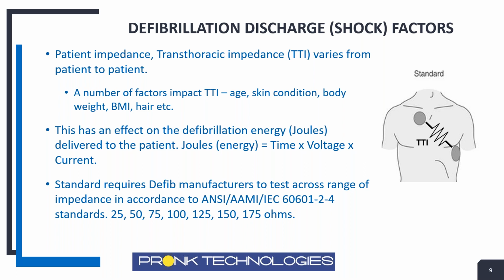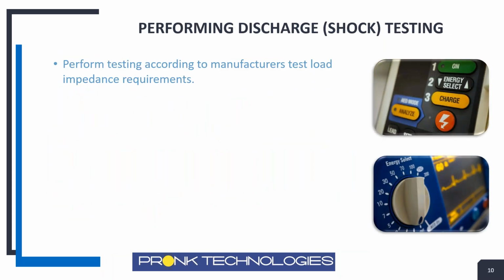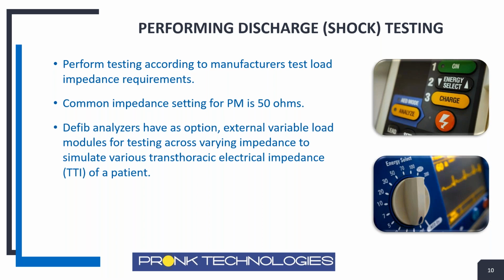So when we're servicing these devices, it's important that we have that in the back of our minds and that we verify what impedance load the manufacturer wants me to use to service this defibrillator. The most common impedance is 50 ohms. Most all defibrillator analyzers have an impedance set for 50 ohms, and that's designed for PMs, and that's generally the standard. But if you're servicing a device and there's a question about how it performs energy-wise, energy delivered, or maybe you've done a repair to the circuit that affects or dictates the energy being discharged, it is important to consider testing across different impedances.